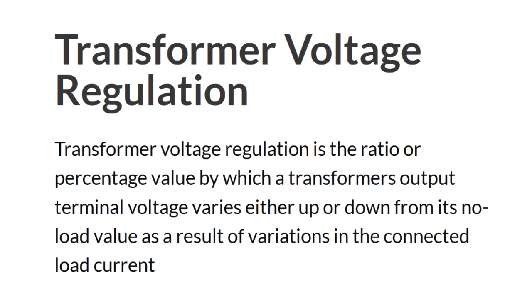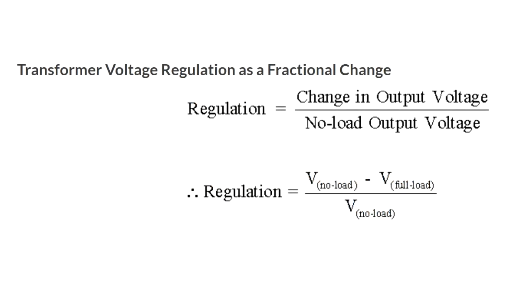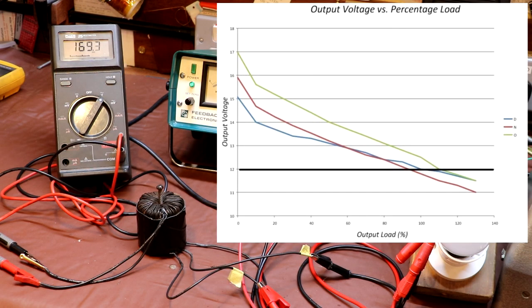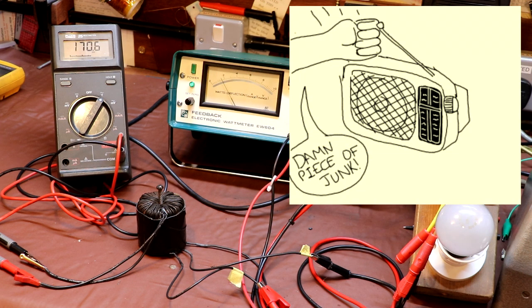So the next test that we're going to do is to investigate the voltage regulation of the transformer. Voltage regulation is a measure of how well a transformer will maintain a constant voltage over a range of load currents, and I think it's probably one of the most important transformer parameters. Now, for most transformer applications, when you load up the transformer and draw current from it, you wouldn't want the secondary voltage to drop, because if the voltage dropped, the equipment you're powering may not work properly.